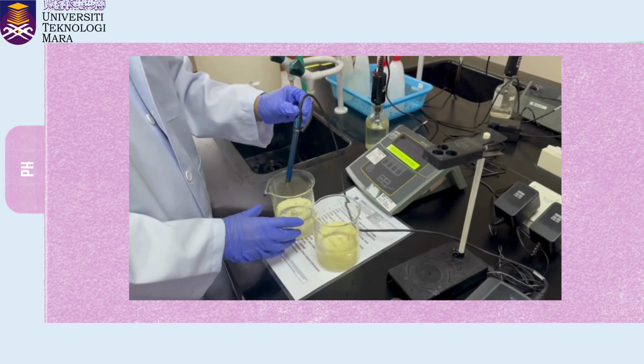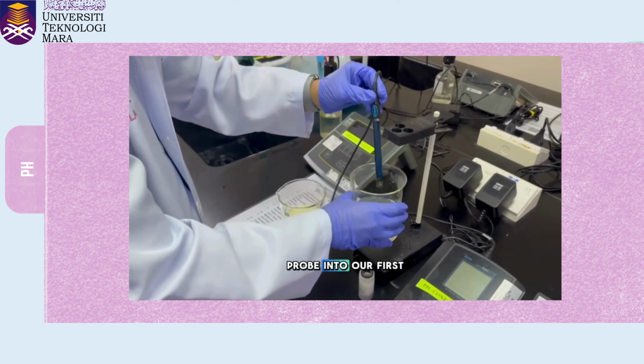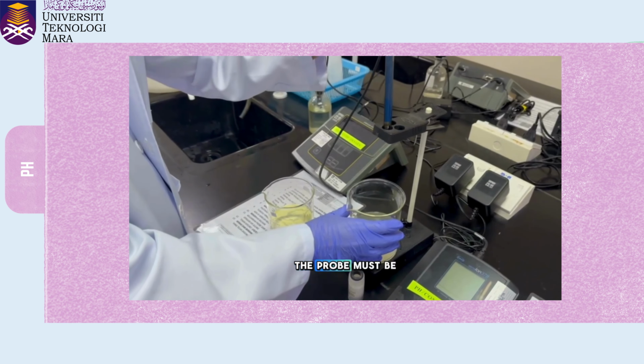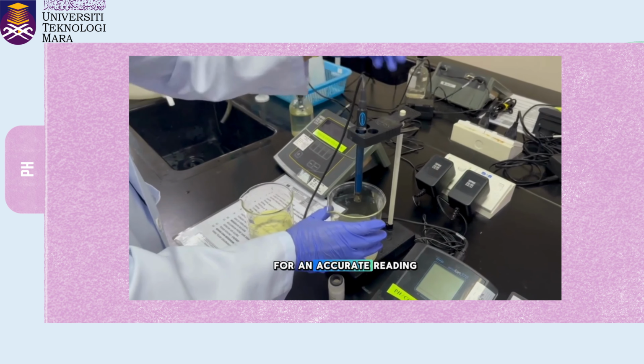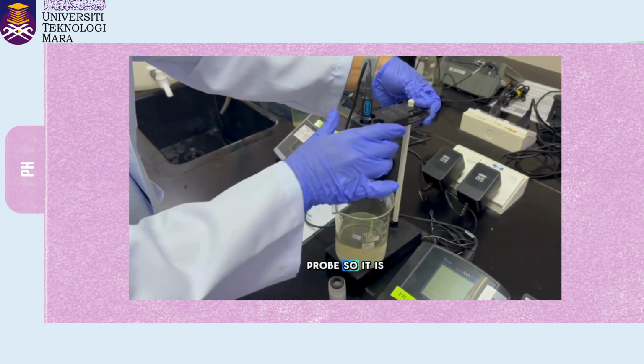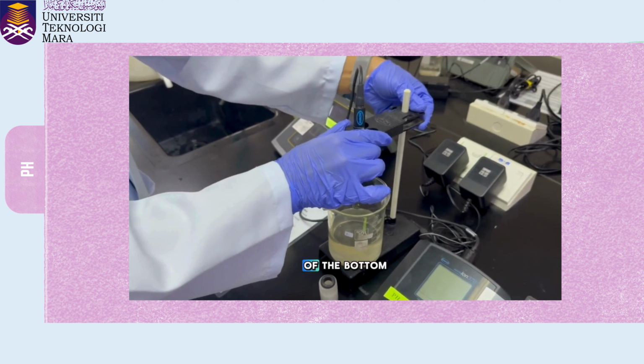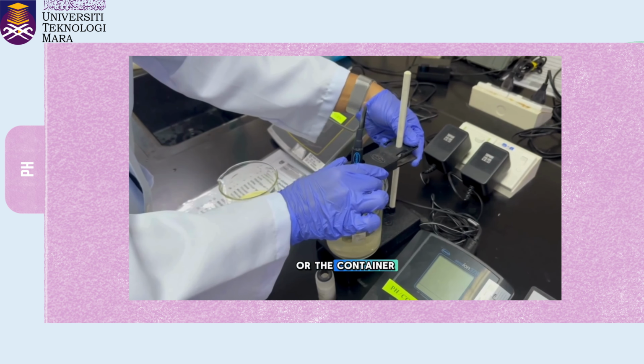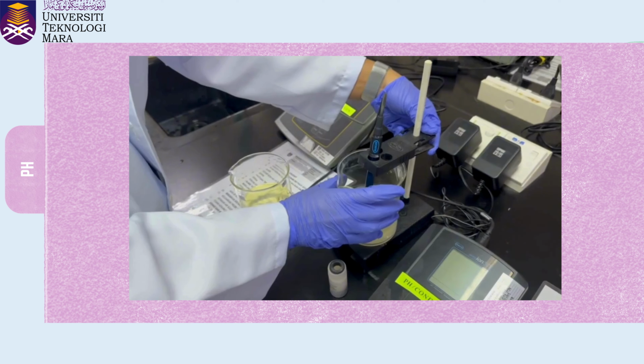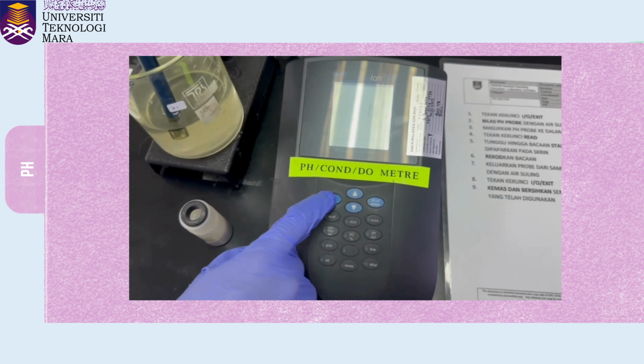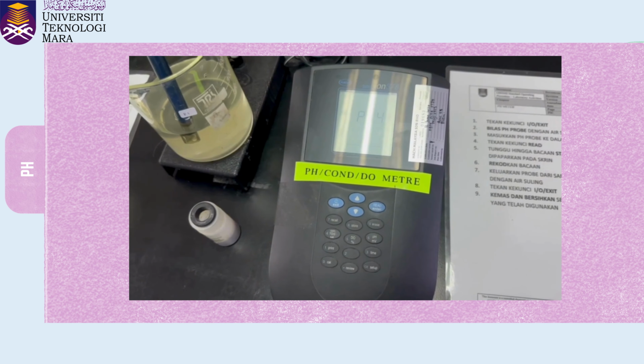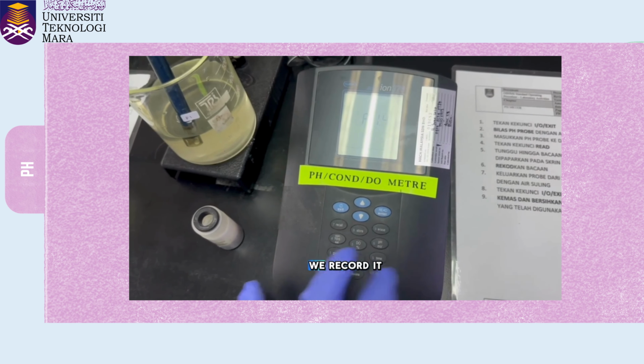After cleaning, we gently insert the probe into our first water sample. The probe must be fully submerged for an accurate reading. Then we adjust the probe so it is steady and not touching the side or the bottom of the container. Once it is in place, we switch on the pH meter and allow the reading to stabilize. When the pH value is steady, we record it.